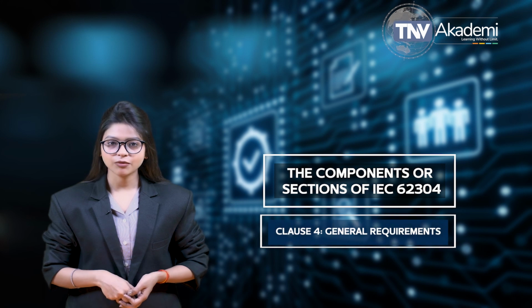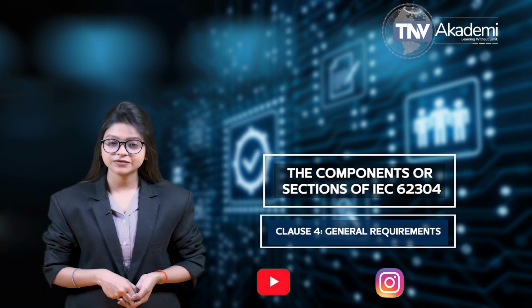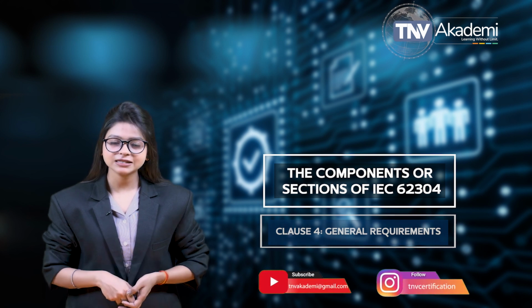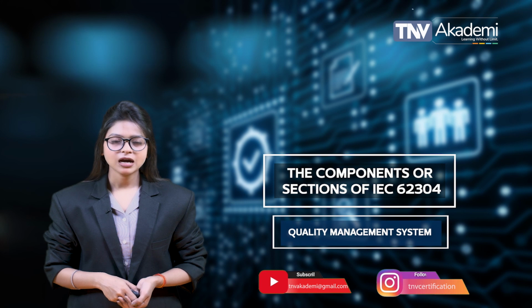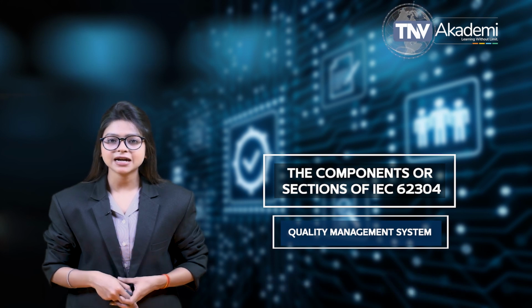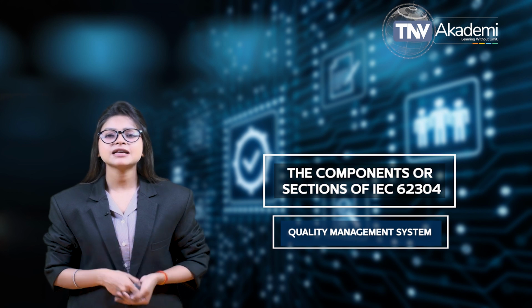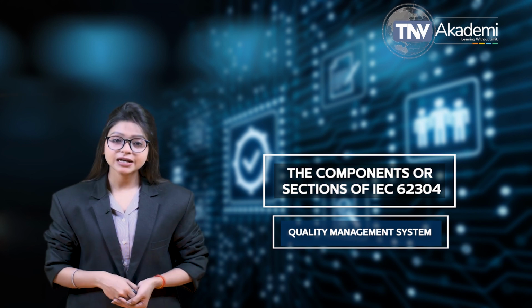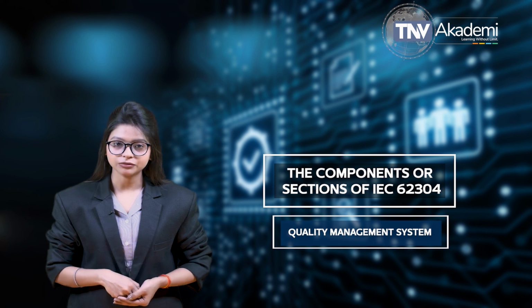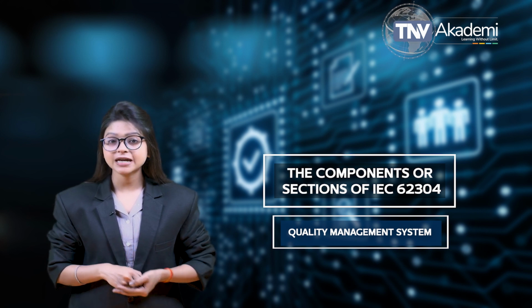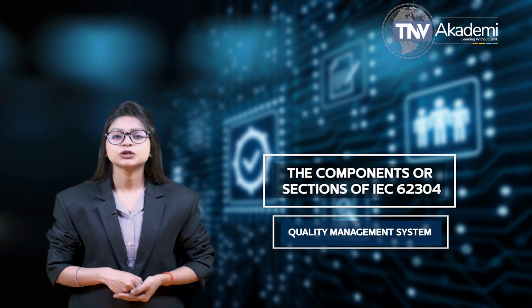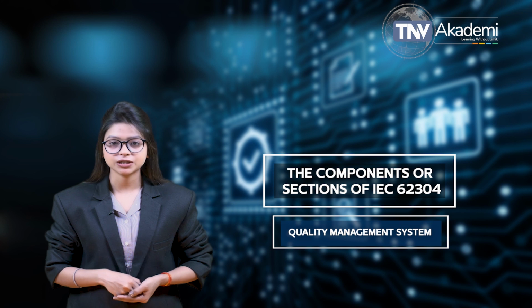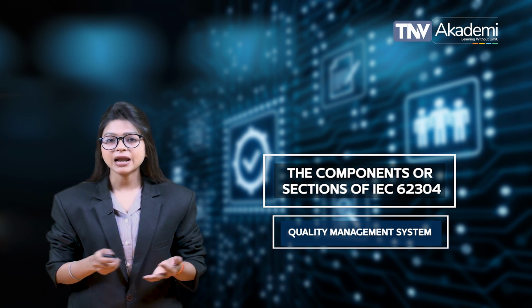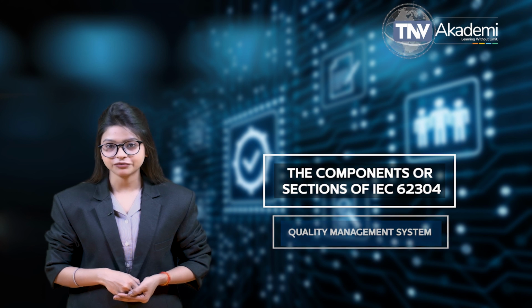Clause 4, general requirements. Clause 4 specifies the need for a quality management system, risk management, software safety classification, and handling of legacy software. Quality management system: ISO 13485 is the international standard for quality management systems for medical device manufacturers. Compliance with other national regulations for QMS is allowed. For example, in the US, the Food and Drug Administration, FDA, currently utilizes 21 CFR 820. However, there are imminent plans to transition to ISO 13485.